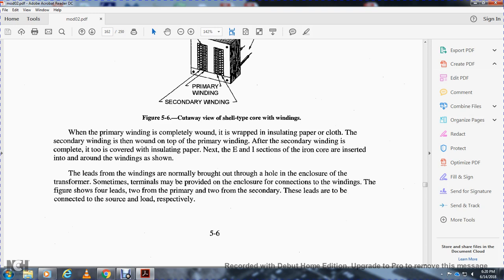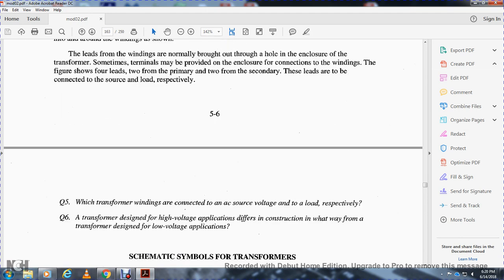When the primary winding is completely wound, it is wrapped in insulating paper or cloth. The secondary winding is then wound on top of the primary winding. After the secondary winding is complete, it is also covered with insulating paper. Next, the E and I sections of the iron core are inserted into and around the windings. The leads from the windings are normally brought out through a hole in the enclosure, and terminals may be provided for connections. There are four leads — two from the primary and two from the secondary — connected to the source and load respectively.